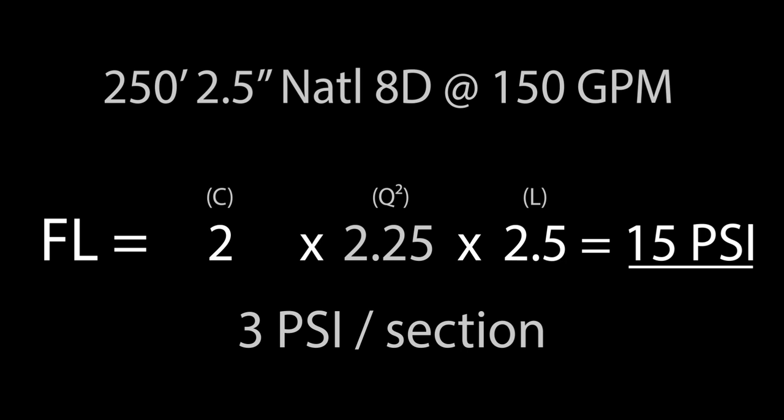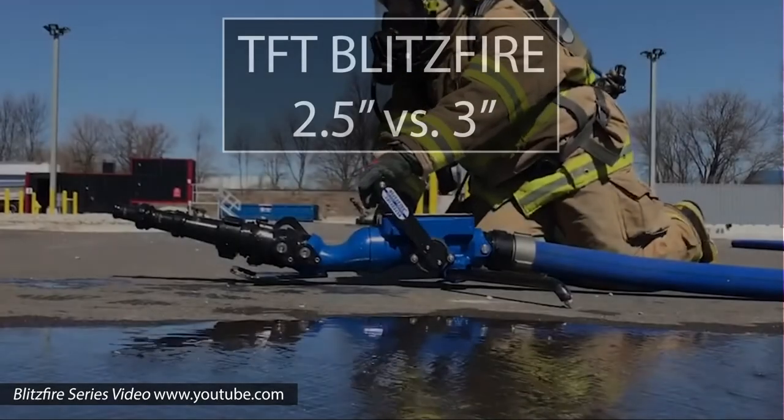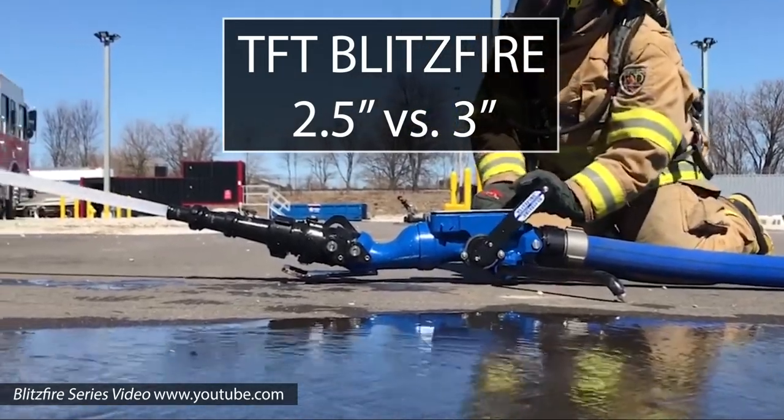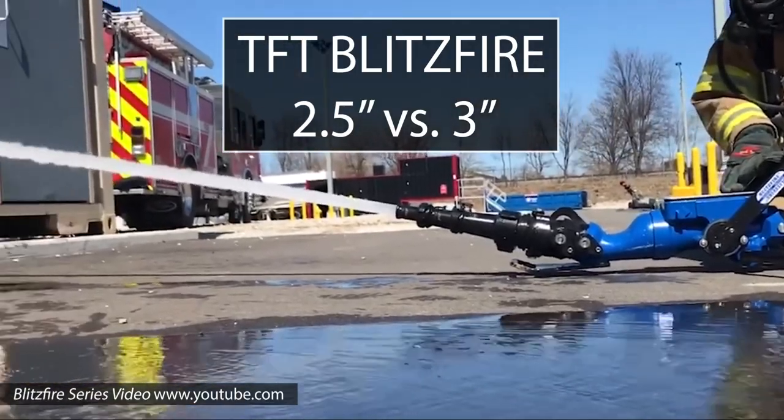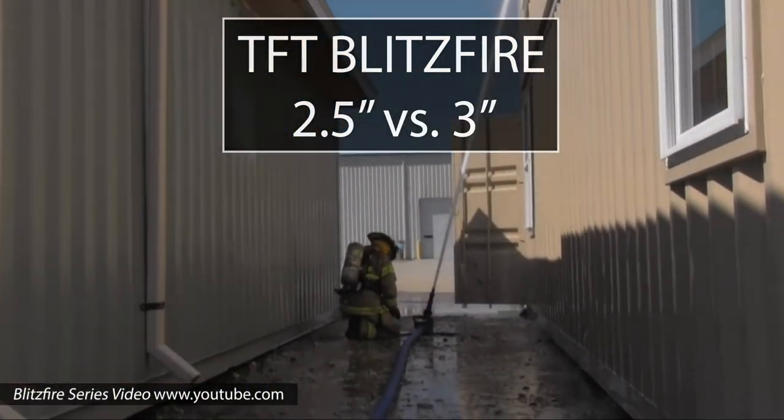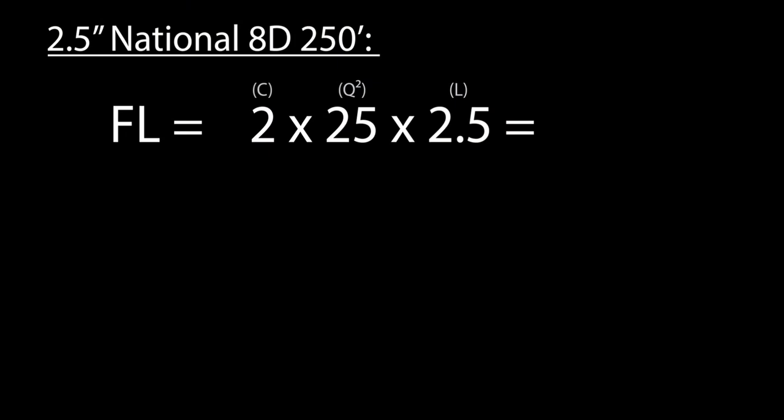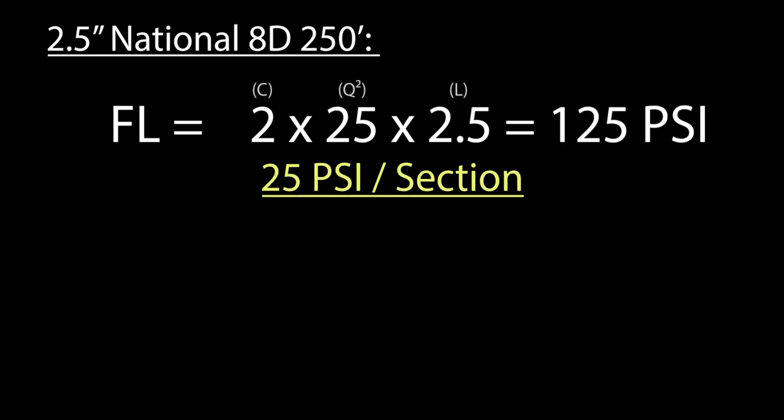So let's look at what happens when we supply a blitz fire with 500 GPM through 2.5 inch compared to 3 inch hose. Using our formula, we can see the theoretical friction loss for our 2.5 inch hose comes out to 25 PSI per section.